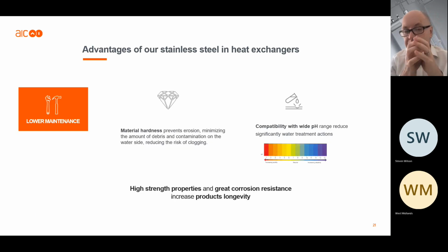Lower maintenance. The experts tell us when you look at the pH chart that stainless steel is more stable than aluminium, for instance, where it's got stability in the pH chart between 4 and 9, whereas aluminium is much less than that, maybe between 5 and 7. Okay, so what that allows is lower maintenance, so we don't have to dose it as much or as frequently. So we don't need to use as many chemicals going through the boiler with this stainless steel heat exchanger. Okay.